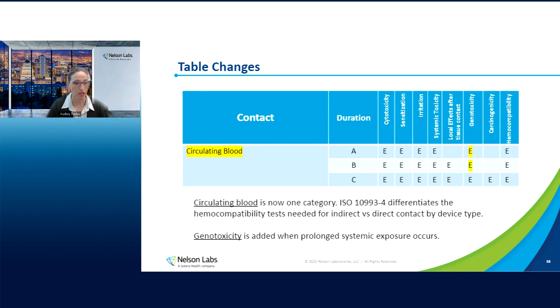Okay, the next table change is for circulating blood. So this is now one category for part 1, because 10993 part 4 differentiates which type of hemocompatibility testing you need to have. And so if you have circulating blood, we're going to get more of that evaluation from 10993 part 4. So we don't have to define that as much here as we did before. And again, genotoxicity is added when prolonged systemic exposure occurs. So we've added it for B, which is prolonged exposure. And then for A, this is for short-term exposure.